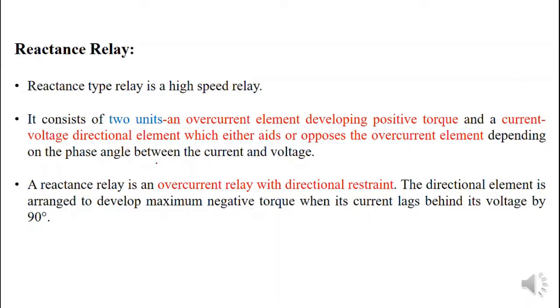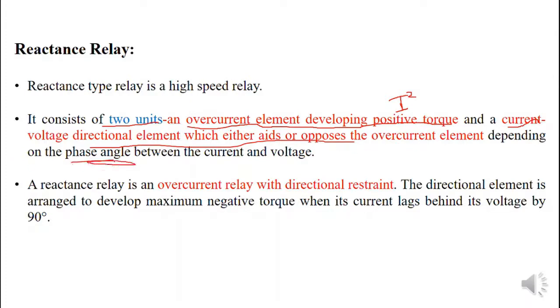The second type of distance relay is the reactance relay. Similarly, it will contain two units. The first operating quantity is the overcurrent element, which produces positive torque directly proportional to the square of the current. The second unit is a current-voltage directional element, which will either aid or oppose the overcurrent element depending on the angle between voltage and current. A reactance relay is also called an overcurrent relay with a directional element; the directional element develops maximum negative torque when the current lags behind the voltage by exactly 90 degrees.